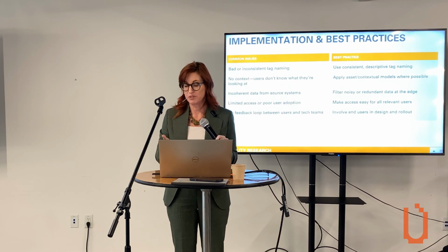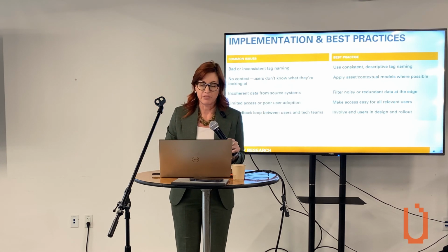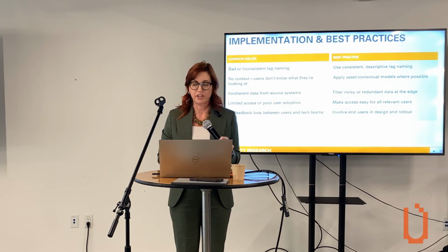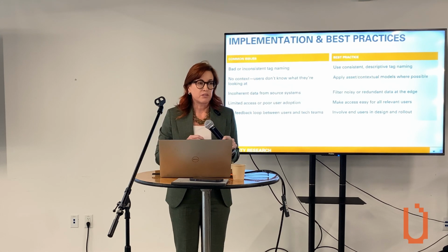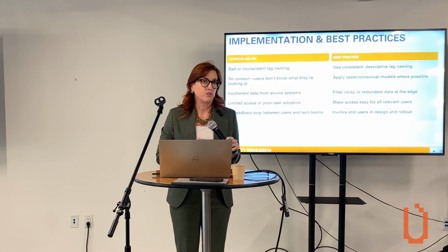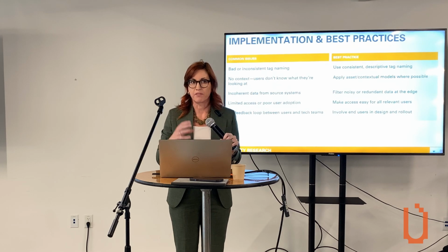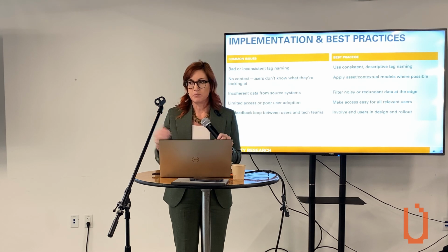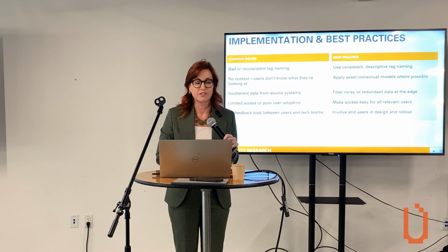And that's just a minimum, right? If everybody did that, pretty soon we've got 20 or 30 tags that mean the same thing. Names matter. Don't make people guess what they're looking at. That leads to multiple tags for the same thing. One of the ways that we've found really successful to deal with this is something that we call an asset hierarchy. So it's really just a way of organizing your tags so that when you're developing a name, it follows a system that anyone can learn, and then it helps them understand what each tag means, and then that helps prevent the creation of additional tags.